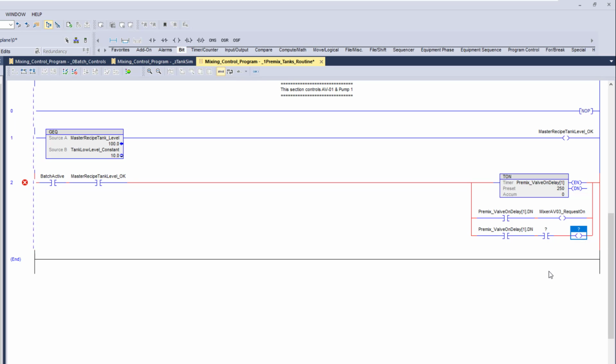Now this bit, so what we're going to do is we're going to say AVO, okay, so we're saying the timer's on, and we're going to request that the AV03 cuts on. Now when AV03 cuts on, the timer's already going to be done. Then when AV03 cuts on, we're going to turn on the AV01. Now AV01, now take in consideration, each one of these valves will be air-driven valves. They'll be basically controlled by air, right? So they are solenoid valves hardwired to a real-world output, right?